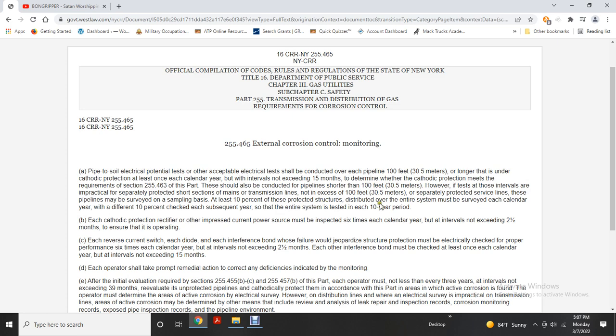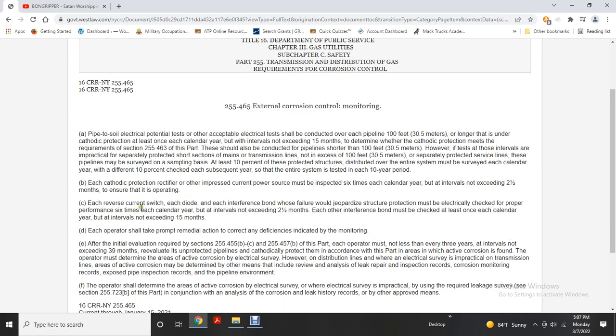Each cathodic protection rectifier or impressed current source must be inspected six times each calendar year at intervals not exceeding two and a half months to ensure proper operation. Each reverse current switch and each interference bond whose failure could jeopardize structural protection must be electrically checked for proper function six times each calendar year at intervals not exceeding two and a half months. Each other interference bond must be checked at least once each calendar year at intervals not exceeding 15 months.